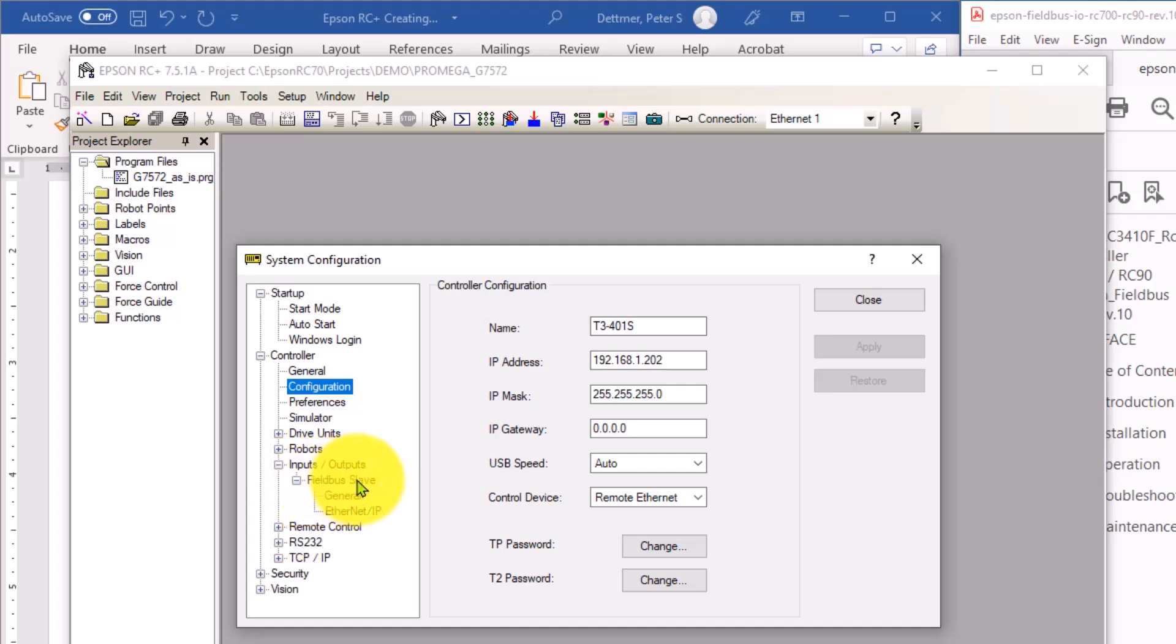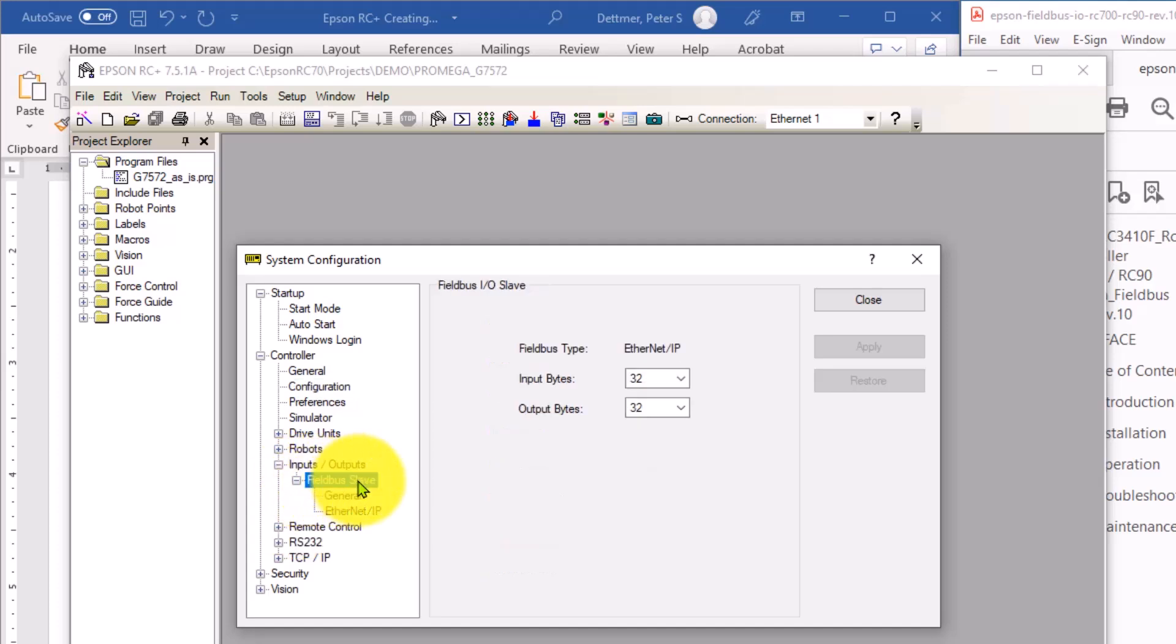And within the field bus device, you set up the input bytes and output bytes. Again, this is how many bits of inputs can be sent between the PLC and the robot. And this setting has to match the Ethernet card configuration on the PLC.